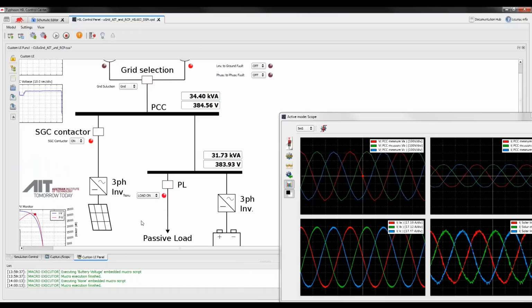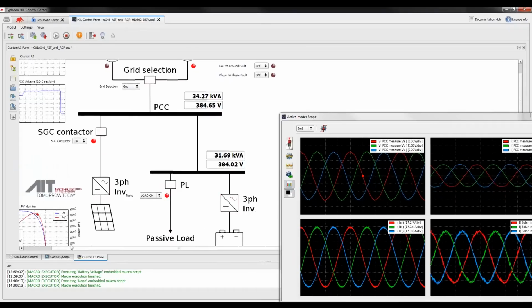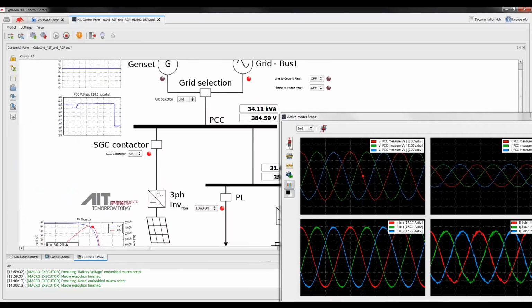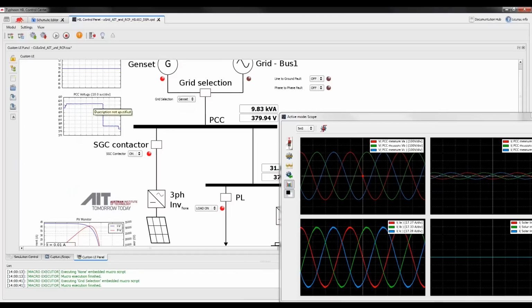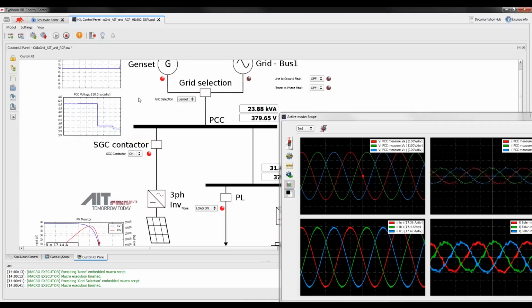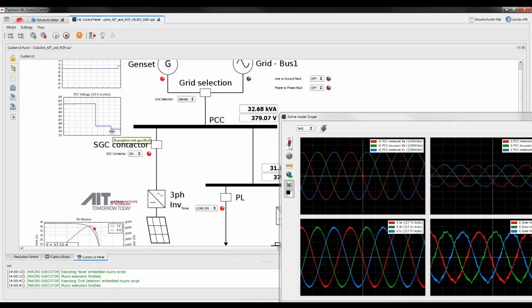Simple event when we are introducing the load. So for example, now the passive load is introduced directly to the battery. You can see here immediately that as we're introducing the load, we have the immediate voltage drop, and frequency of course is stable because the frequency here is the frequency of the grid. But what is really interesting is what's going to happen when we switch now from grid tie to the islanded mode. Immediately as we're switching, we can see that the voltage drop is significant simply because there is a long line, and the long line actually provides a big voltage drop.